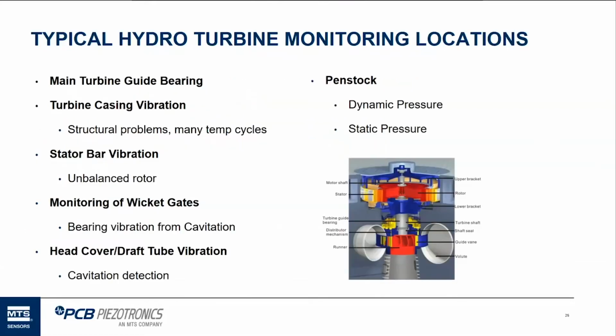These are the typical items that are monitored on a hydro unit: the main turbine guide bearing, turbine casing, stator bars, wicket gates. Wicket gates are sometimes monitored for vibration, not always, but a wicket gate can cavitate, causing a lot of vibration problems and damage if it's not monitored. The head covers and draft tubes are also looked at for cavitation with vibration sensors. And the penstock is usually monitored for changes in pressure, or static pressure level, to make sure that the flow's right and not changing a lot, for proper operation of the hydro turbine.